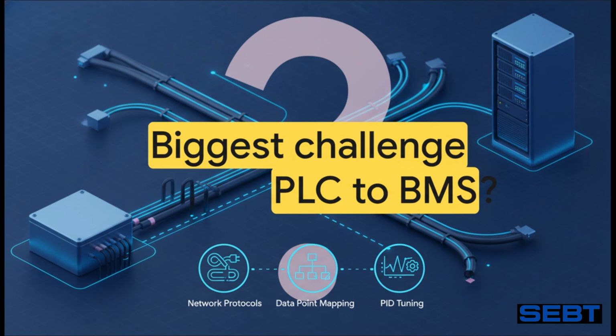As we wrap up this explainer, I want to leave you with a bit of a provocative question to chew on. When you look at the sheer complexity of the field wiring, the ultra-fast deterministic logic of the PLC, and then that macroscopic, overarching network of the BMS, what do you think is the biggest technical challenge when integrating a newly programmed AHU PLC into a massive, already existing building management system? Is it trying to align those network protocols? Is it meticulously mapping hundreds of data points? Or maybe it's ensuring that the new PID tuning actually respects the legacy systems already in place?